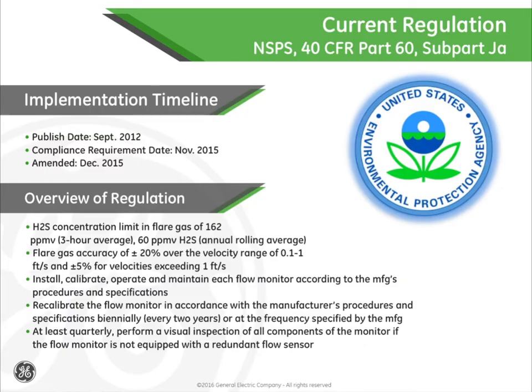One of the most recent regulations passed in the United States by the EPA is referred to as NSPS-JA, or New Source Performance Standard, subpart JA. This regulation went into effect in November of 2015. NSPS-JA was written to control sulfur emissions in refineries. In order to accurately determine the amount of sulfur being emitted, these refineries needed to accurately measure the flare gas going through the line. They also needed to deploy a gas chromatograph and/or sulfur analyzer.